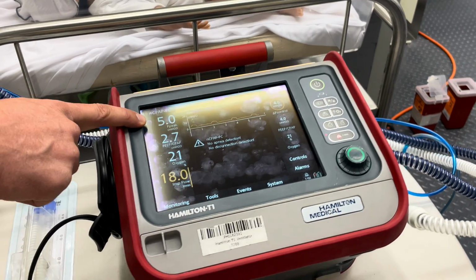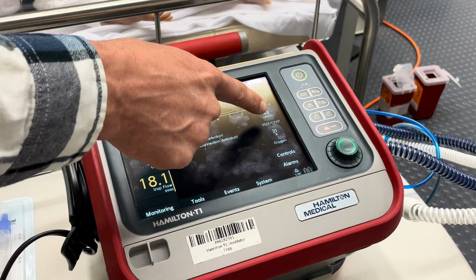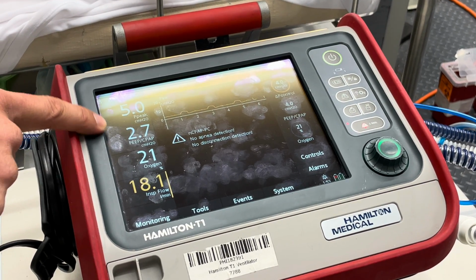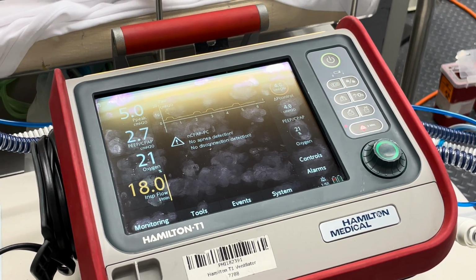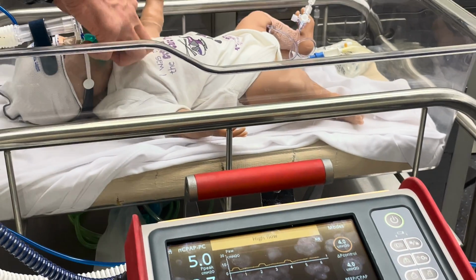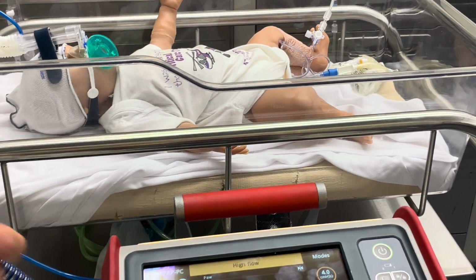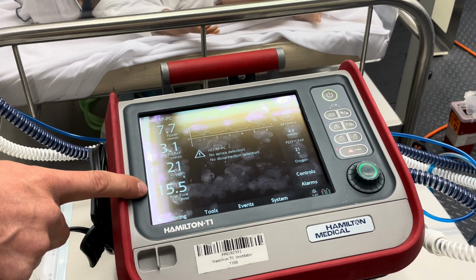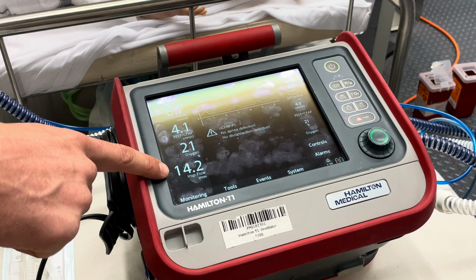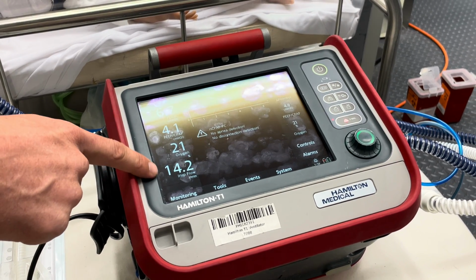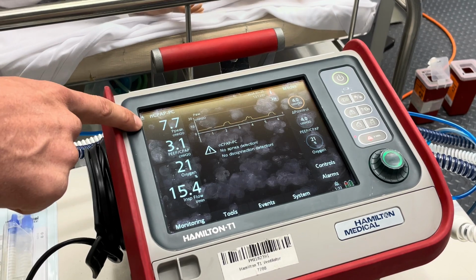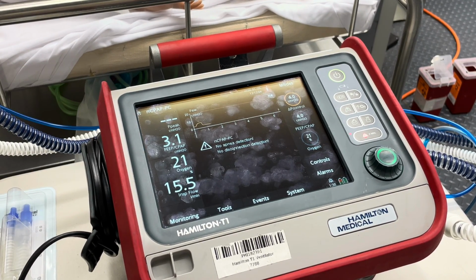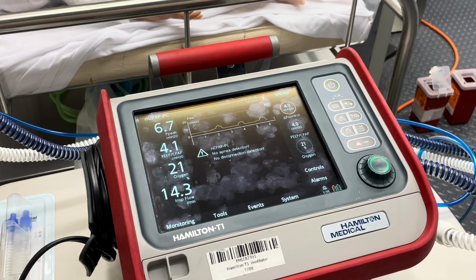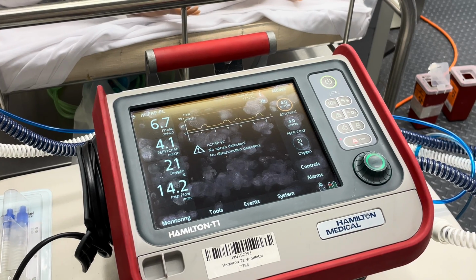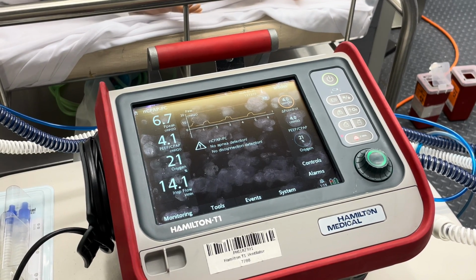Now what we have here is we have a peak pressure, which should be close to what we're adding here. And then we have a PEEP or a CPAP. In this case, we have a pretty big leak. So sometimes if you don't have a chin strap, a pacifier can help address that leak a little bit. And you'll see our pressures come up a little bit, and our high flow warning went away. This is just flow rate, just like you'd expect to see on a high flow cannula. And it's going to increase the flow rate in order to reach the target pressures that you've set on the ventilator. Since there's no flow sensor, there's no flow waveform, there's very few alarms, there's no apnea detection. It's a very, very simple approach to doing nasal CPAP or BiPAP.